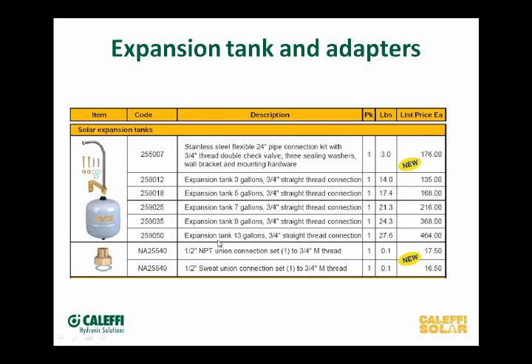We offer different tank sizes. Larger sizes have a base mount so they can sit on the ground instead of hanging off a bracket. You can also gang these together — tee them together — as long as you set the pre-charge pressure the same on all of them. Our expansion tank kit includes a double check valve — one checks the fluid in the tank and one holds the fluid in the system. You break the brass union in the center to remove the tank without losing any fluid from either side.